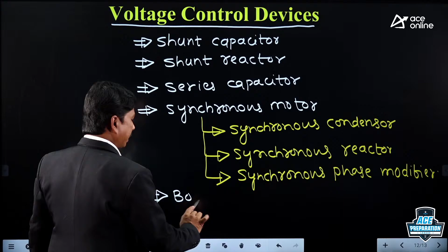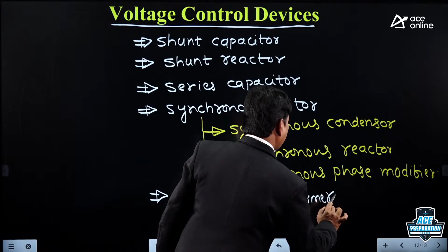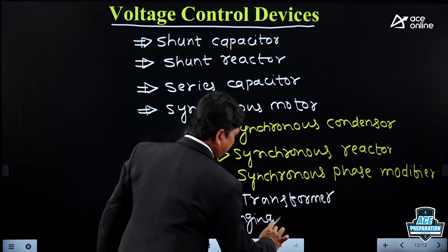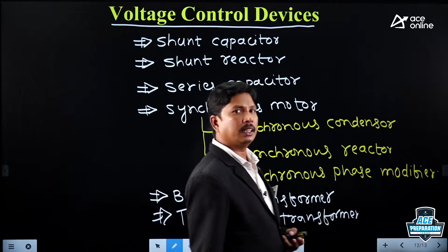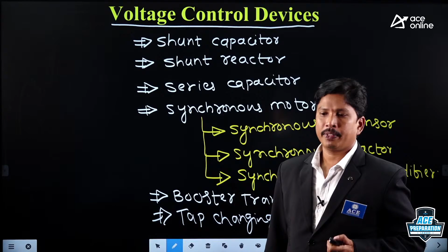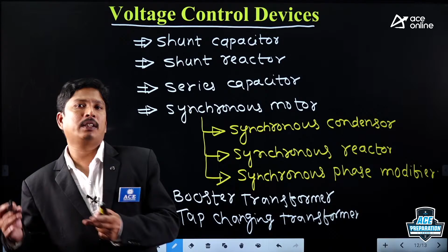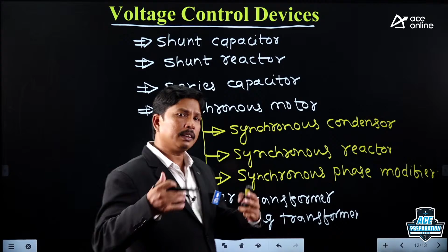Along with this reactive power control device, we are having directly voltage control devices also, like a booster transformer, by using transformer technique only. So booster transformer, and also we will be having tap changing transformer. So these are the voltage control devices we are having, students. In these devices, we have to go in detail, and see which device is used to increase the receiving end voltage, and which device is going to reduce the receiving end voltage, right? At which condition we are having over voltage at the receiving end, at which condition we are having less voltage at the receiving end, right? All those conditions we have to analyze, and we have to connect the suitable devices at that particular location. Clear everybody?